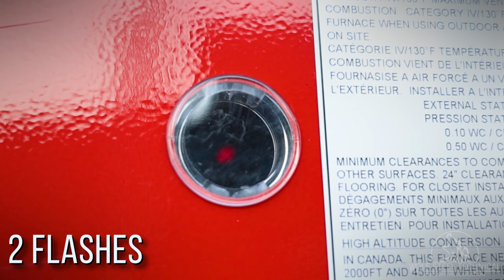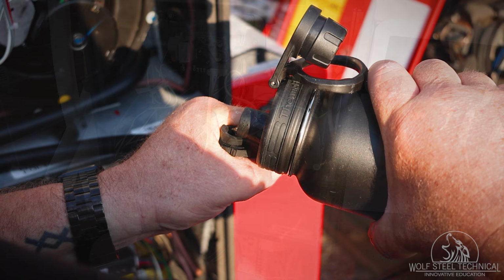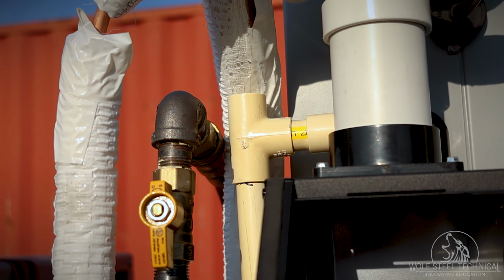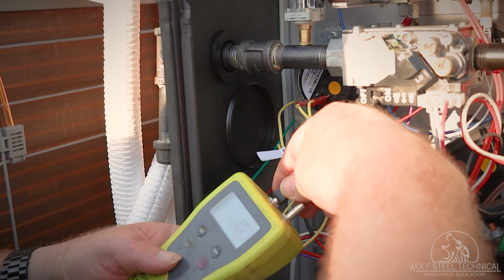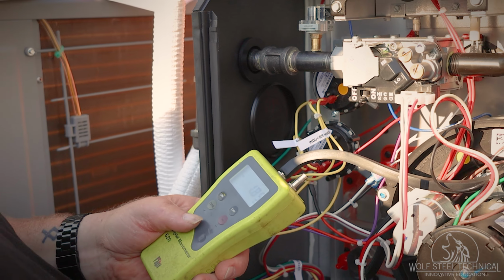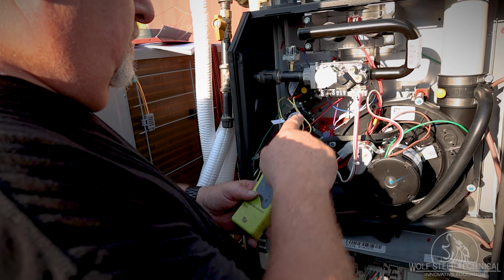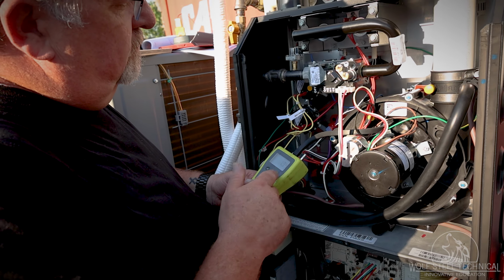2 flashes signifies a pressure switch issue. First, check the condensate trap on the side of the furnace. Ensure it is clean and primed with water and that it has an atmospheric vent. Next, use a manometer to ensure the correct pressures are coming to the switches. The pressures observed should be above the rated value shown on the back of each switch.